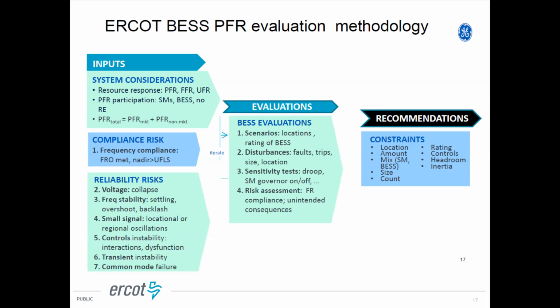So, interactions between BESS and synchronous machines. So far, our IBRs were not modeled, so until now we've not been able to look at BESS and renewable energy interactions, but hopefully in the future we'll be able to. Also to see if there is any misbehavior - is any limit cycling happening, is any fault-ride-through getting triggered that it shouldn't. So we were looking at those kinds of things too, any system separation. One of the concerns I mentioned was they have potentially upcoming large batteries that will want to interconnect that can offer 100% of their rating.